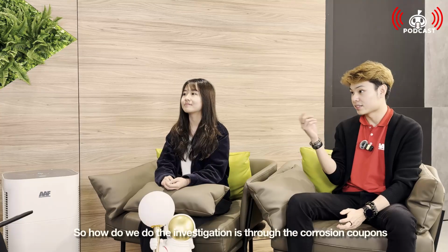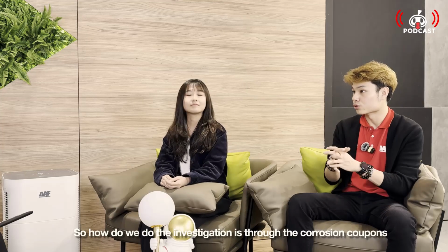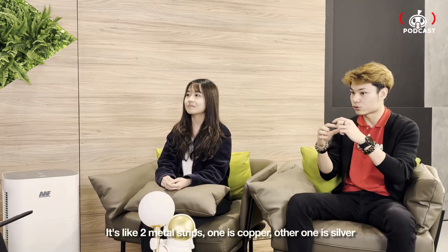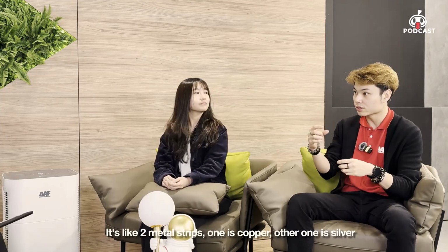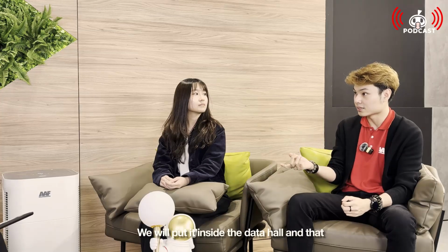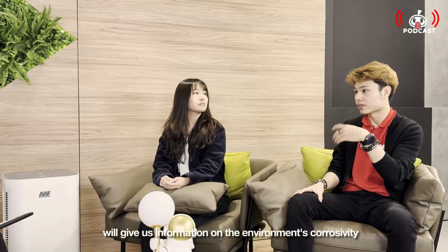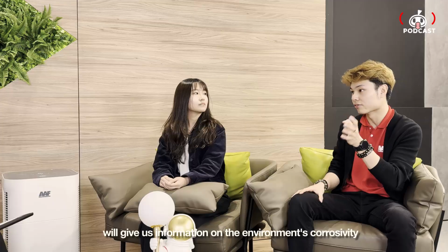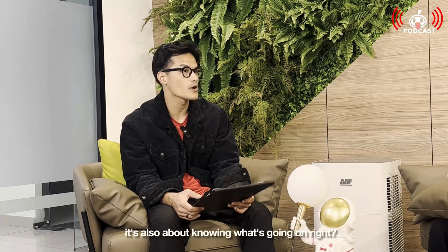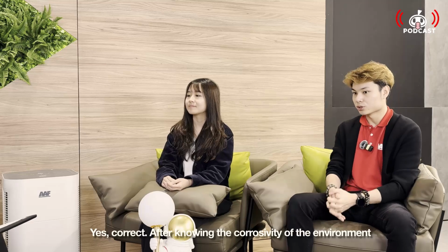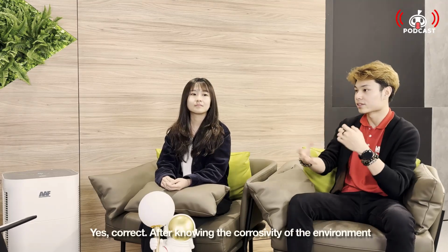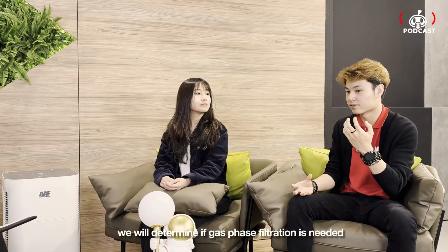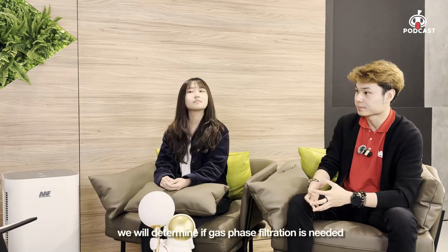So how do we investigate? It's through corrosion coupons. They are like two metal strips, one copper and one silver, which we put inside the data hall, and they give us information on the environment's corrosivity. I see. So it's not just about prevention, it's about knowing what's going on, right? Yes, correct. After knowing the corrosivity of the environment, we will determine if gas phase filtration is needed.